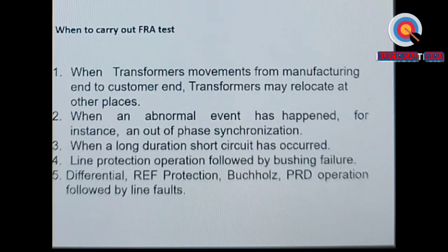So we will inadvertently close the circuit breaker in phase opposition, and this will cause a major short circuit inside the transformer. If this type of event has happened, then again we carry out the SFRA test and check whether transformer integrity is there or it has suffered some damage. Another case is when a long duration short circuit has occurred. Now, how long is long? In an electrical system, when we talk about protections, we talk of isolating faults within 100 to 200 or maybe 250 milliseconds. We are talking in terms of milliseconds and not seconds.